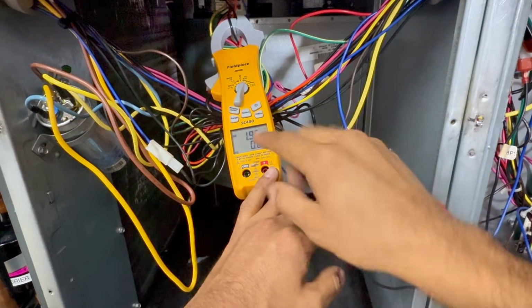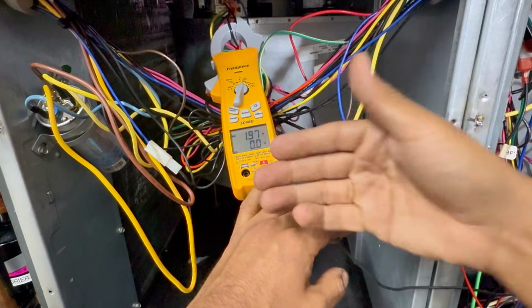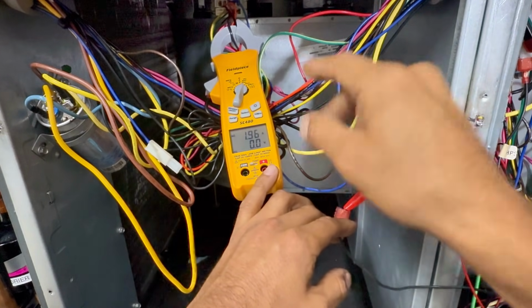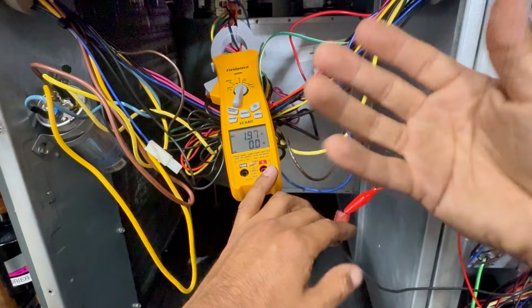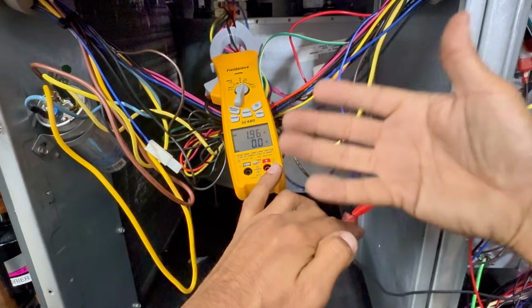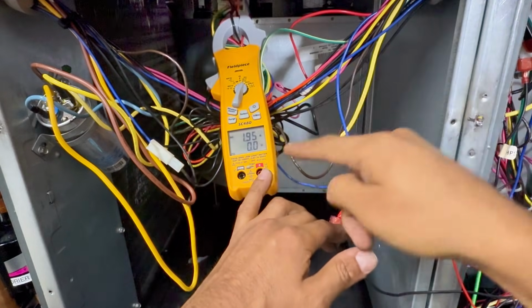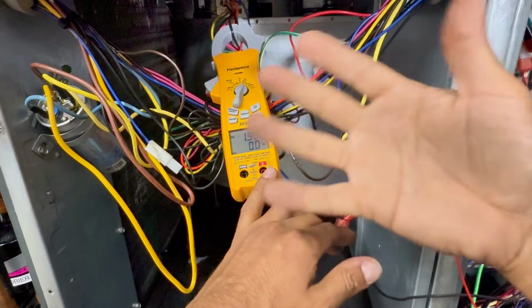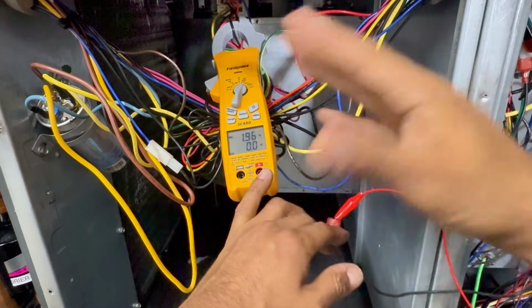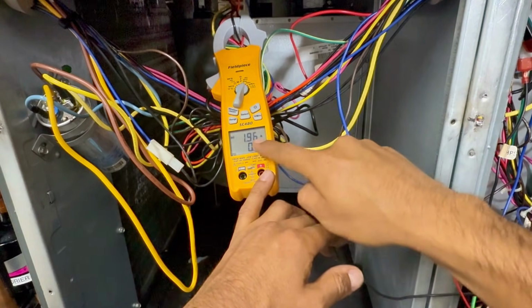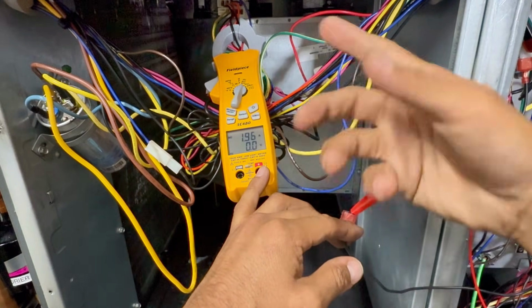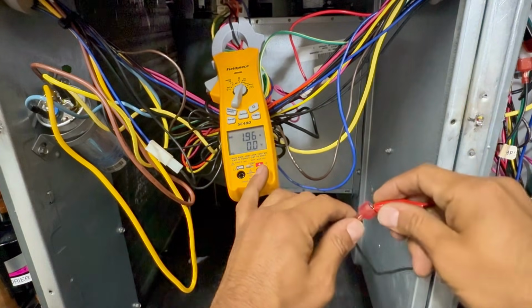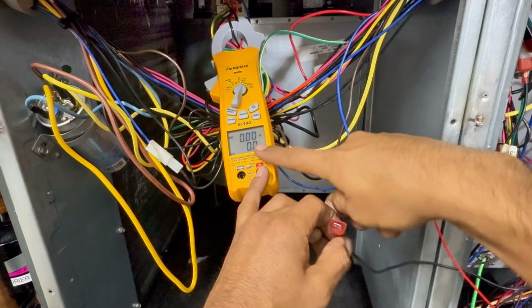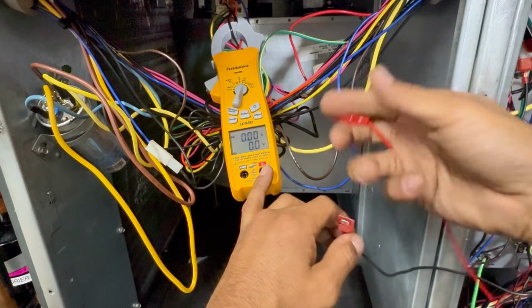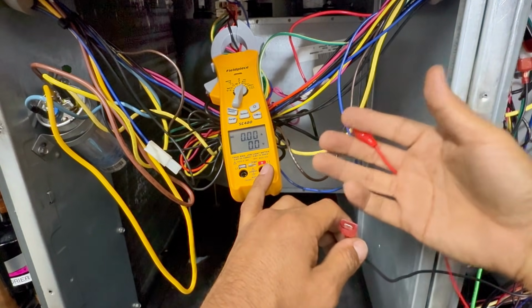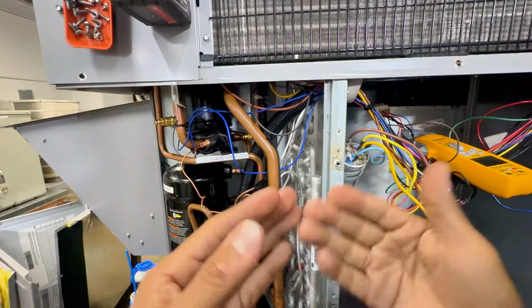So by you checking the amp draw, that's another way you can check how well that motor is operating, right? Because if it's in the high speed, it should be pulling a lot more amps, or at least close to that full load amps. So obviously this panel right here is open, and you get the point, right? It's not gonna be pulling what it should be, but it's pulling close to 2. But you see, I just wanted you to see, now that it's on, we're getting amp draw. And then once I disconnect the 24 volts, it's gonna go to 0 because there's no current going to it. It's not on. And if it's not on, no current. No current, no work. Okay, now we're gonna check the condenser fan motor.